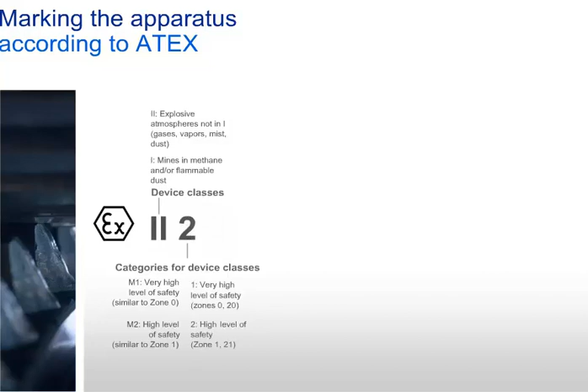To distinguish the use in gas or dust explosion-proof areas, the equipment is marked with G for gas and D for dust. Ex stands for explosion-proof apparatus. The ATEX directive marks different ignition protection classes depending on the protection principle. An ignition protection class is a special measure applied to electrical apparatus in order to prevent ignition in ambient explosive atmospheres. Ignition protection classes are divided into electrical and mechanical ignition protection classes.